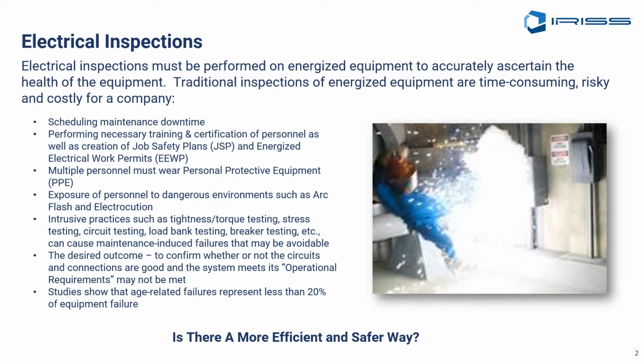Electrical inspections have to be performed on energized equipment in order to get useful information. This is true for most types of electrical inspection: infrared, ultrasound, partial discharge testing. A lot of these cannot be done on equipment when it's de-energized because you're just simply not going to see anything. Energized inspections are time consuming, they can be risky for your personnel, and they can be costly for your company if they don't actually catch the problems that you're trying to detect.